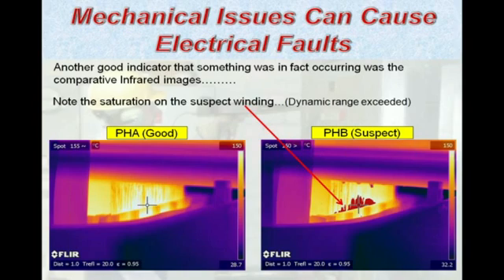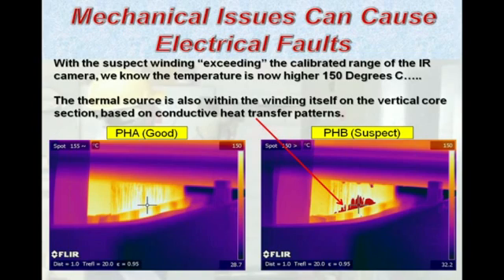The important thing is looking at the direction of the thermal or heat transfer. It is coming from down inside the device. That's interesting because we have winding insulation down there, we have shims and supports. This is the type of stuff that, if it begins to move, can begin to cause damage to the winding insulation.